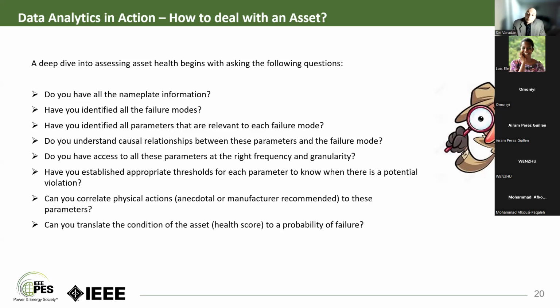But there are other parameters, for example DGA, which is relatively slower. When you see changes in the dissolved gas in a transformer, that's indicative of a failure coming, but not in the next 8, 16, or 24 hours - it's something further out, maybe 2, 3, or 4 years. Nonetheless, you have to know the characteristics of these particular parameters so you know what to do with it.